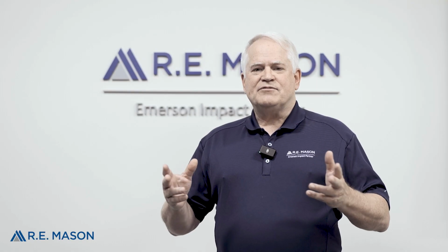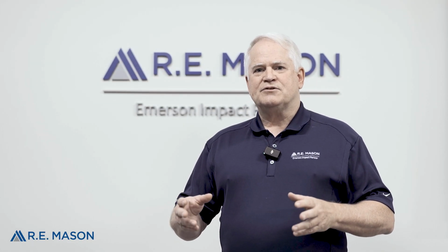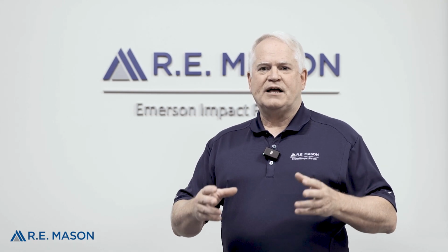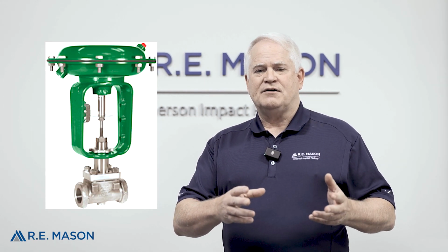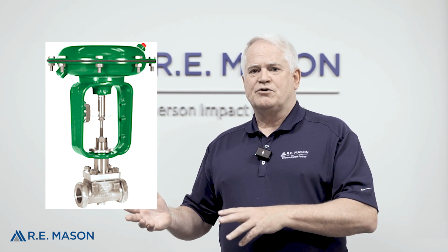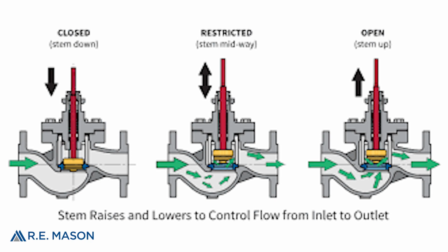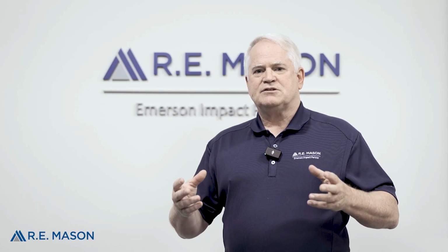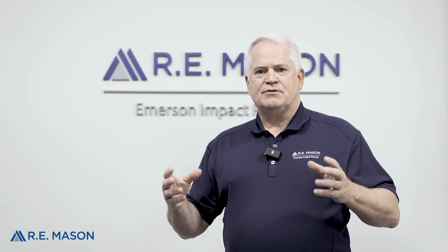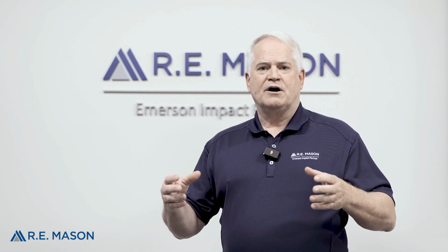So as we look at cavitation in control valves, we'll see that there's quite a bit of difference between a globe style or linear style motion valve versus a rotary valve. In a globe style valve, the flow is moving and takes a 90-degree turn to enter into the valve, comes through a tortuous path, goes through the port, and then takes another 90-degree turn out of that. So there's a lot of energy dissipated, a lot of pressure that's lost and permanently lost through that device. So it is considered a low recovery valve.